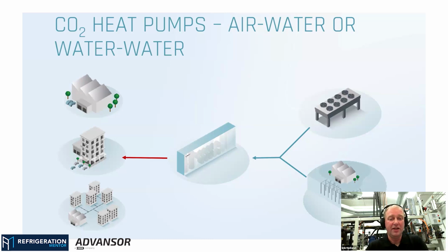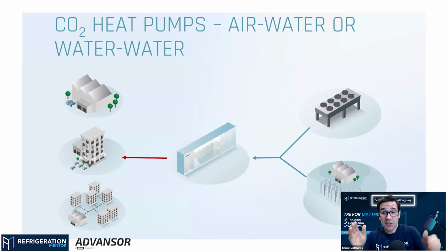The technical part of it is it can happen, for instance, if your return gas sensor on your gas cooler, your drop leg sensor, has fallen off the pipe. It's just hanging, dangling there. Then you get into a situation where the air temperature sensor and the gas temperature sensor have the same value. So now the gas cooler controller thinks that the temperature is satisfied because it can't cool it anymore, so it stops the fans. Yeah, that's huge right there.